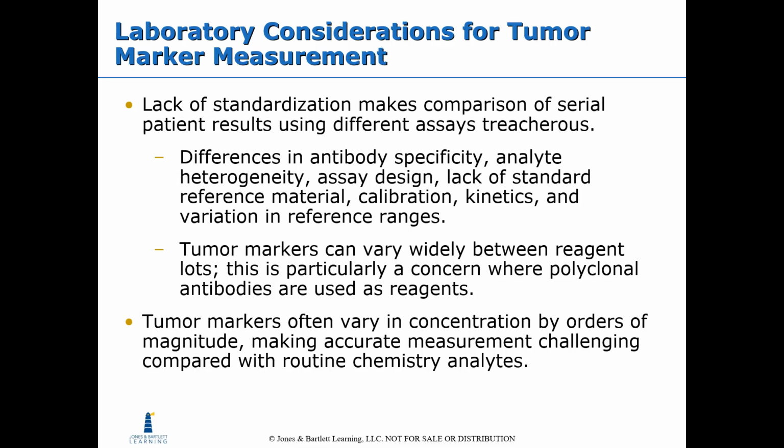Lack of standardization makes comparison of serial patient results using different assays treacherous. Differences in antibody specificity, analyte heterogeneity, assay design, lack of standard reference material, calibration, kinetics, and variation in reference ranges. Tumor markers can vary widely between reagent lots. This is particularly a concern where polyclonal antibodies are used as reagents.